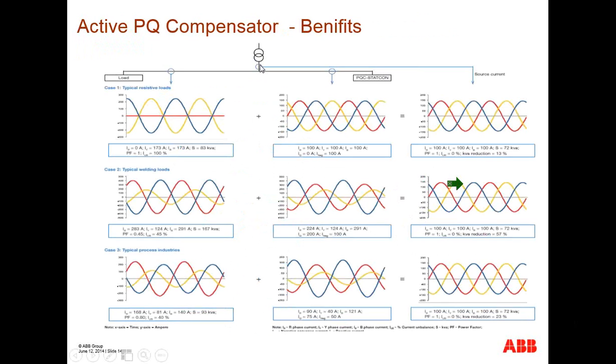Here is an example, a few cases. You have a transformer. There are different types of load currents here. There is one phase where the current is 0, the first phase. The Y and B phases are fully loaded. But if we put the active compensator here, it draws this kind of current. So when we add these two currents, we find the total current coming from the grid is basically balanced current in all three phases and without any reactive power.